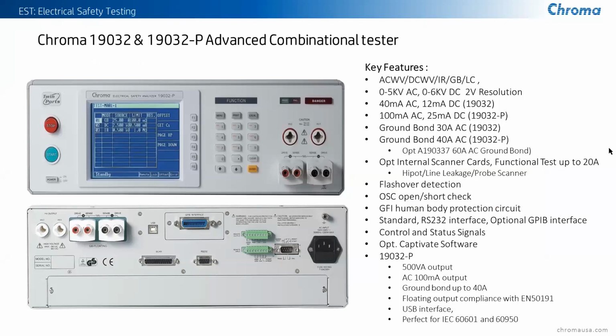To get into more advanced type testing, Chroma offers the 19032 and the 19032P combinational testers. With this one, we can do the standard AC and DC high pot testing and the insulation resistance, but we can also do ground bond and leakage current all in one unit. With this one, again, you get the standard 5 kV AC, 6 kV DC for AC and DC high pot testing, but it also gives you higher current capability for devices that have higher impedance insulation. You get up to the 40 milliamp AC and up to 12 milliamps DC on our standard 19032s. And then with the 19032P, the high power version, all the way up to 100 milliamps of AC current, 25 milliamps DC, ground bond all the way up to 40 amps.